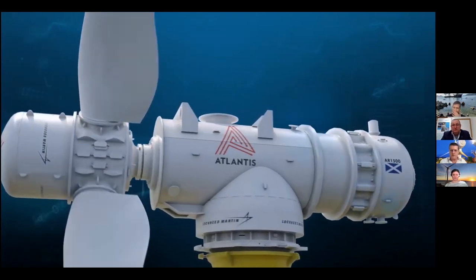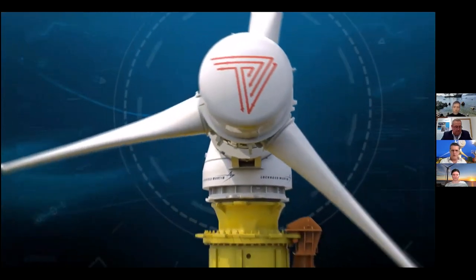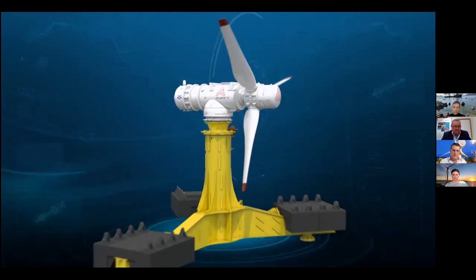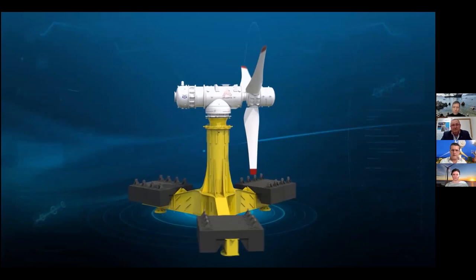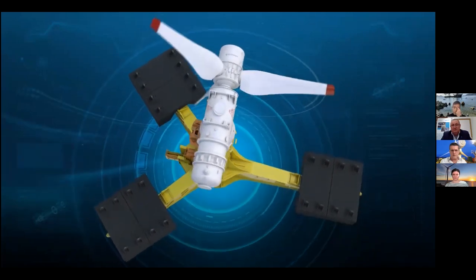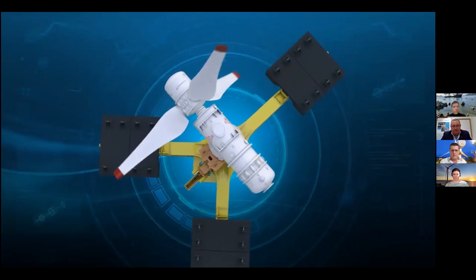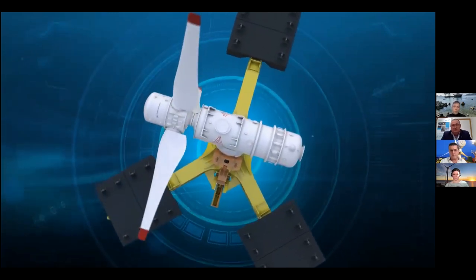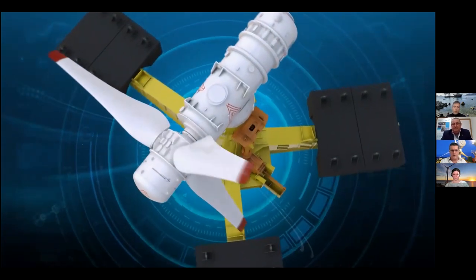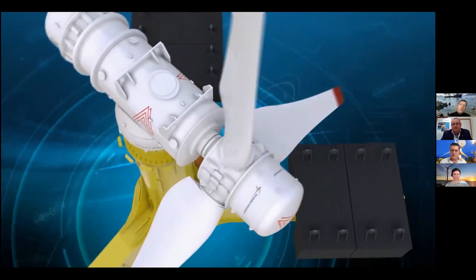We've had some problems with our pitch, Rob. Never buy a hydraulic high-pressure hydraulic rotating pitch if you're a subsea turbine — different maybe if you're floating or a small unit. That's been the main issue; there really haven't been any other major issues. MeyGen's got two Hammerfest turbines on the beach now, and AL is about to go back in and they'll be back up at six megawatts. Depending on your expectations as the world's first array, I think we give ourselves a pass. We'd all like more than 40 gigawatt hours by now — but still, 40 gigawatt hours.